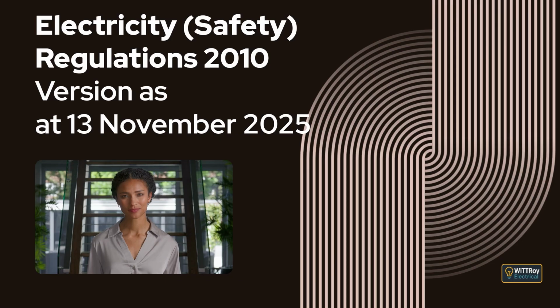This regulation explains that all high-risk prescribed electrical work carried out on a low or extra-low voltage installation, or part installation, must be inspected as required by Regulation 59 or Regulation 60, depending on the situation. It also explains that all high-risk prescribed electrical work carried out on a high-voltage installation must be inspected to verify that the installation complies with ECP 34, and with Regulations 34, 41 Subclause 1, 42 Subclause 1, 43 Subclause 1, and 44 Subclause 1, with references to works treated as references to high-voltage installations.